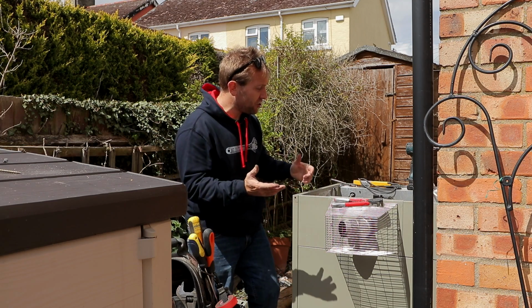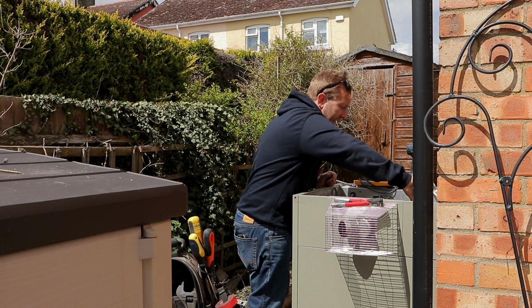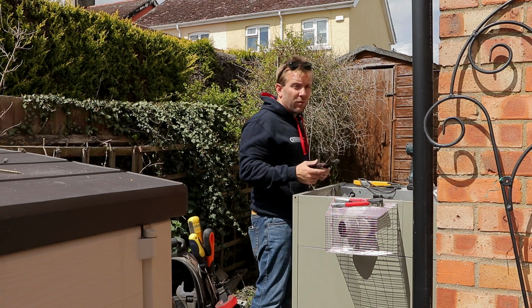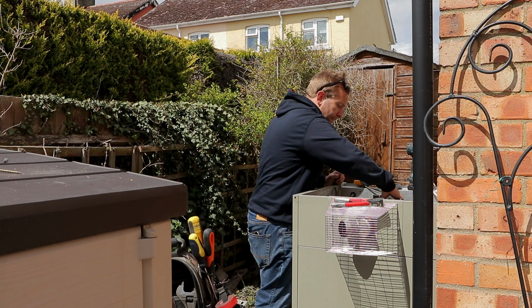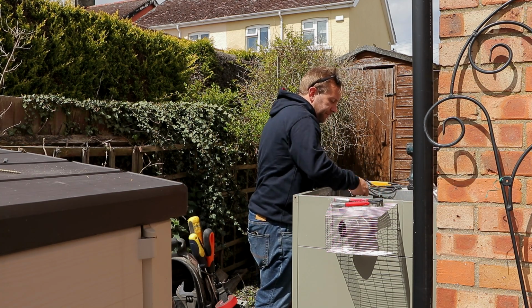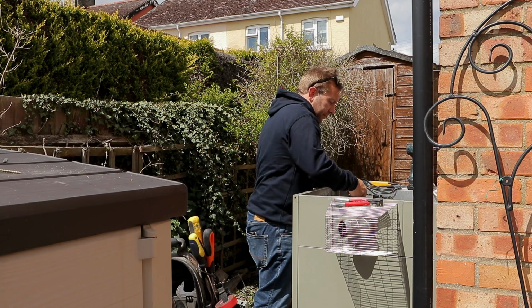The first thing I'm going to do is just shut every valve off at the top that connects us to the rest of the system. We don't want to have to drain the whole system out if we don't have to, because this is usually quite a quick change. So I'm just shutting off the valves now.